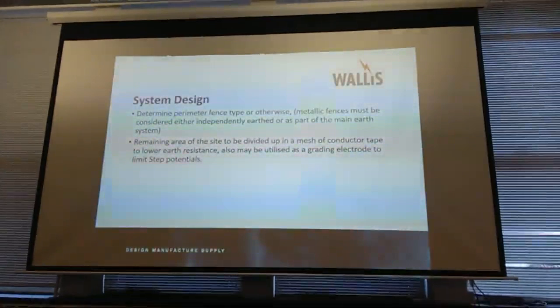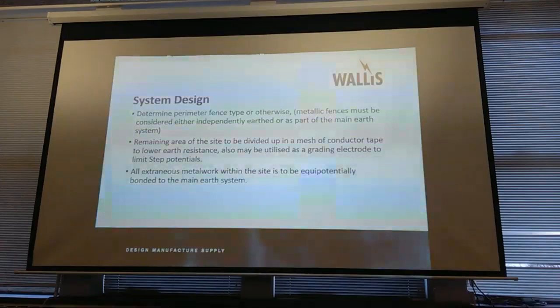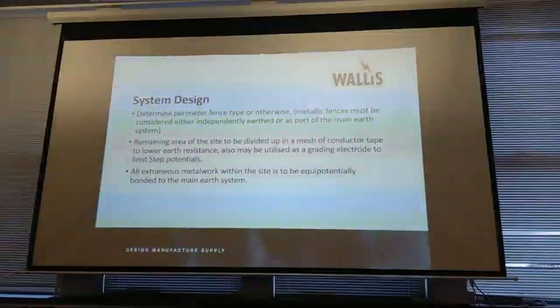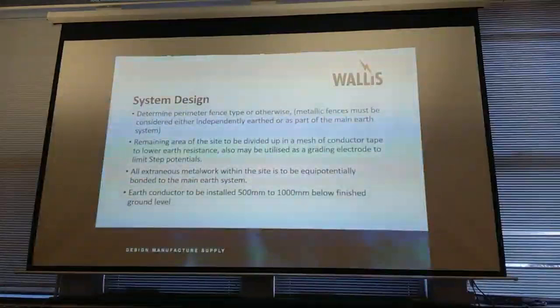The remaining area of the site, you use the site you have to the best of your ability. All extraneous metalwork within the site can be equipotentially bonded. As per everything else that we do, be it LV earthing or equipotential bonding, you're dragging everything to the same potential. If everything's at the same potential, there's no potential difference, no current flow.